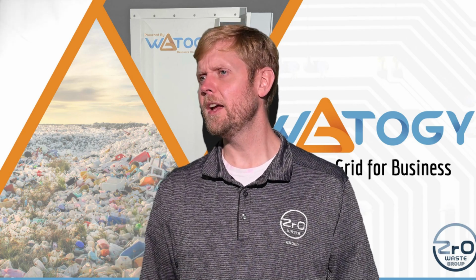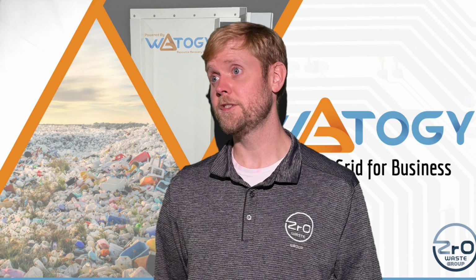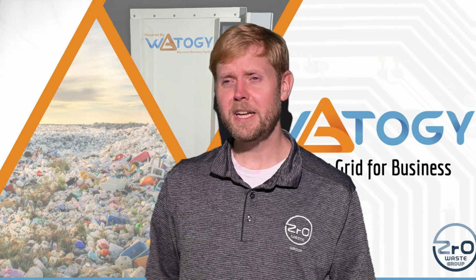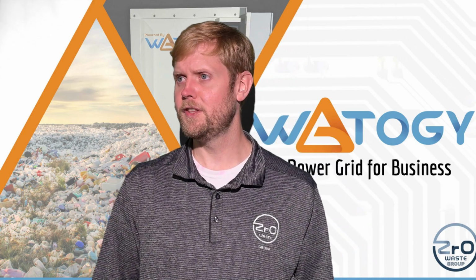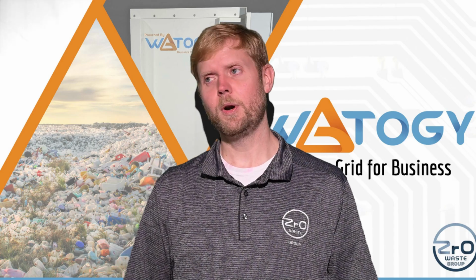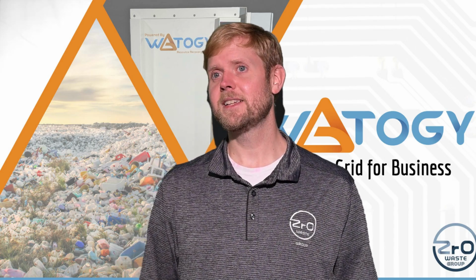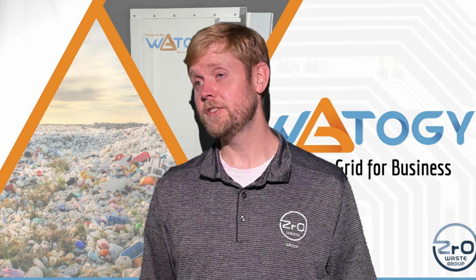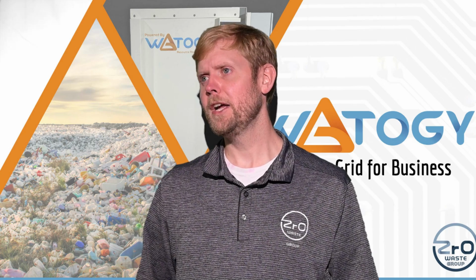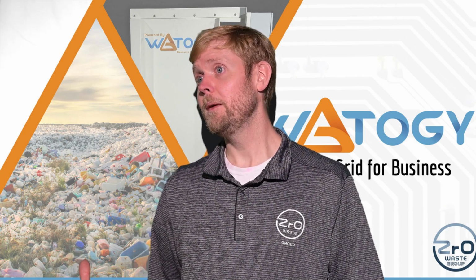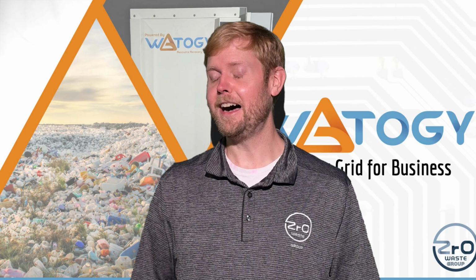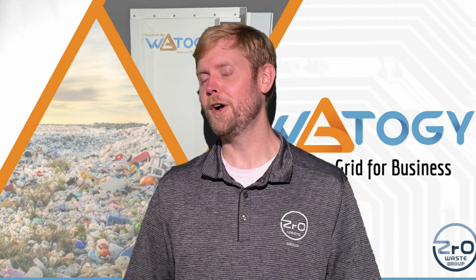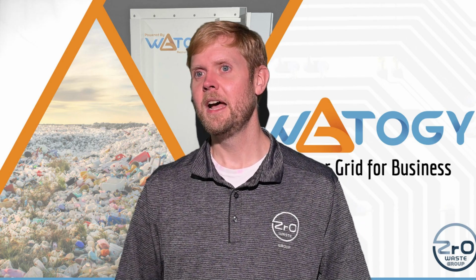It took us again only about three months to build this system, which was maybe about three times the complexity of the Gen 1, so we're rolling. That system demonstrated 8 tons of cooling, and we should be able to reach 10 tons probably by tomorrow, honestly, but we're testing a new oil pump, which I'll get into in a minute.